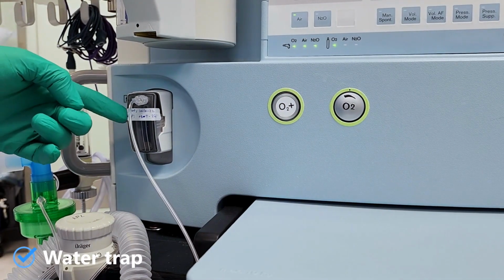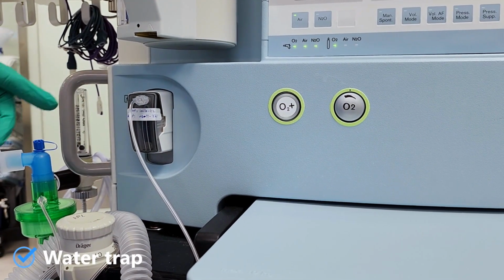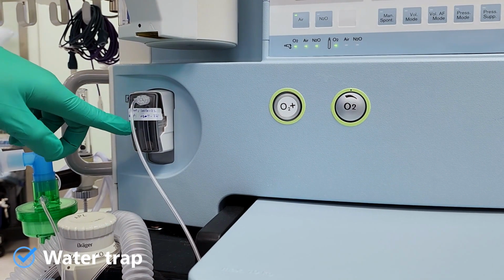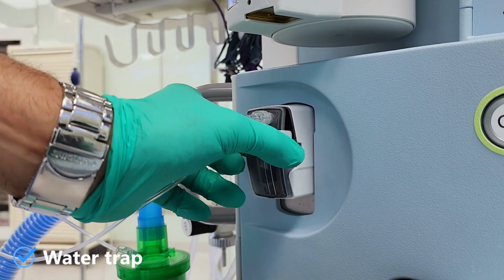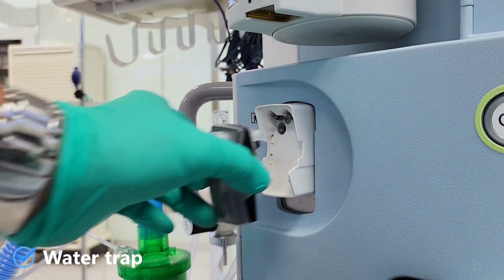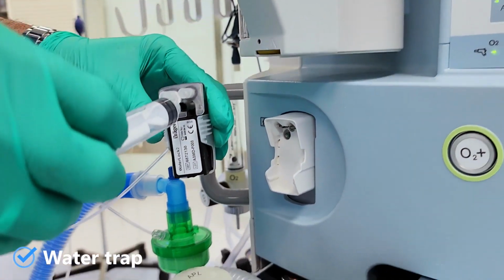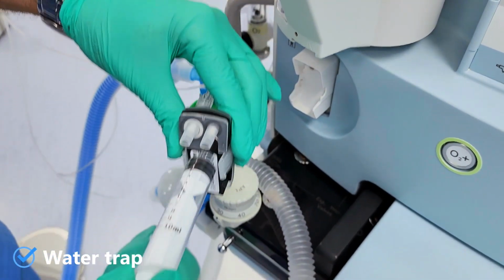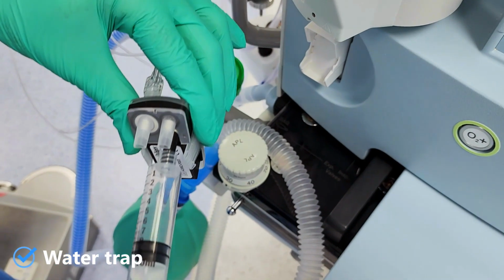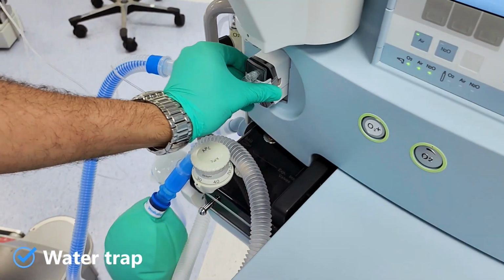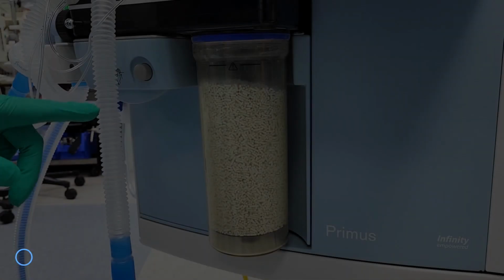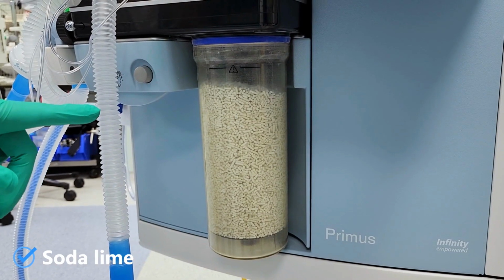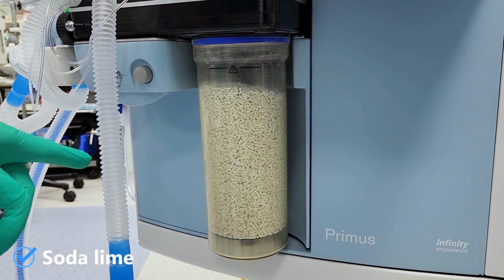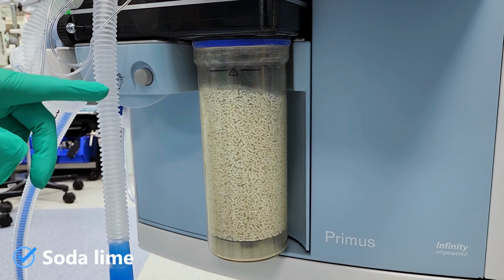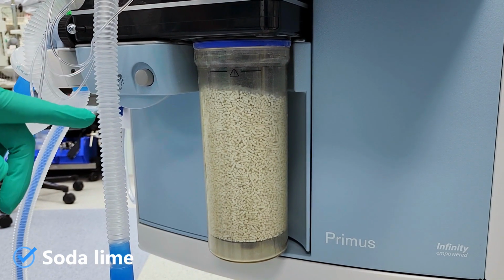Now coming to the water trap. It has to be replaced every 28 days, and the date should be properly labeled. To remove water from the water trap, attach a syringe to the drain port and aspirate. And make sure it is inserted properly. Check soda lime color. According to the manufacturer, the soda lime has to be changed if 2/3 of the color has changed, or if inspiratory CO2 is more than 5 millimeters of mercury, or after more than 4 weeks of use.